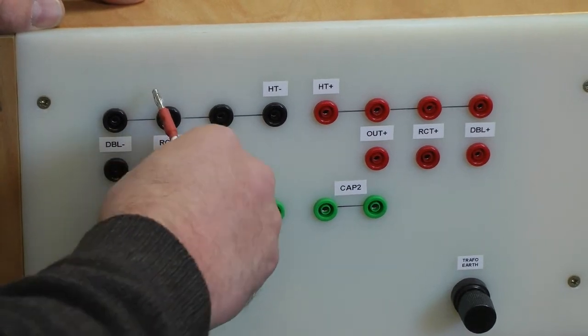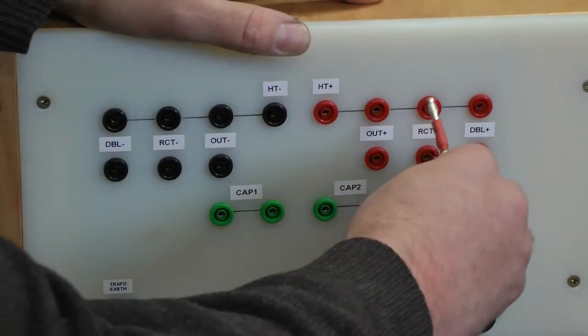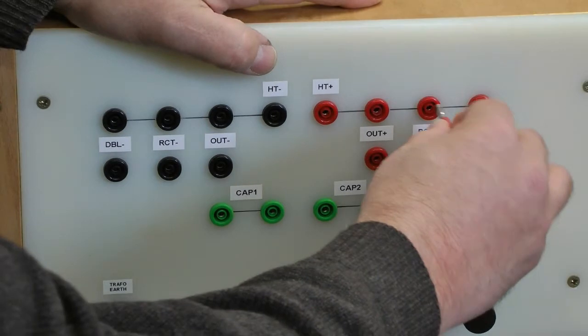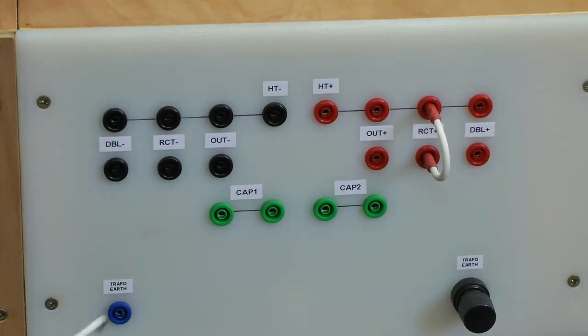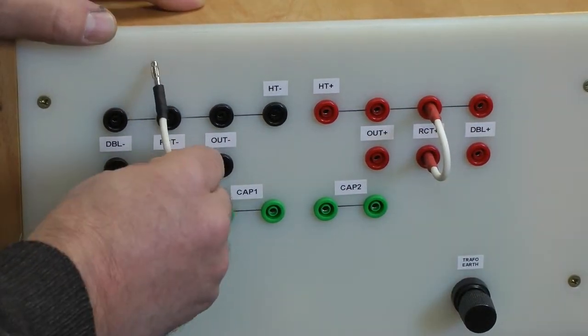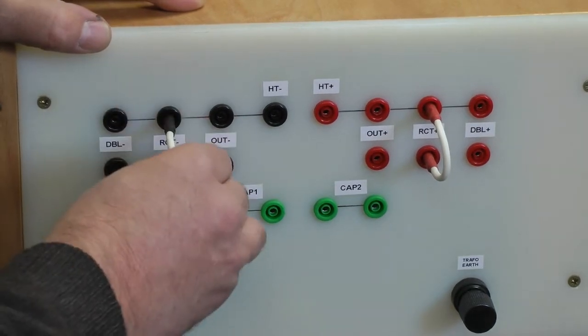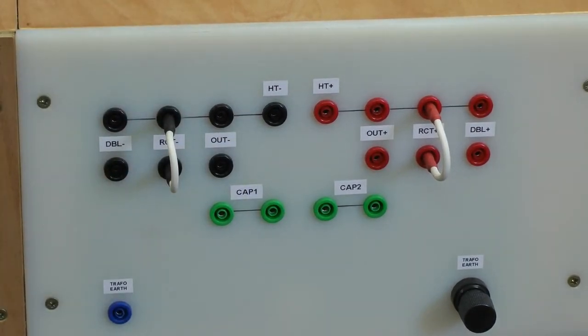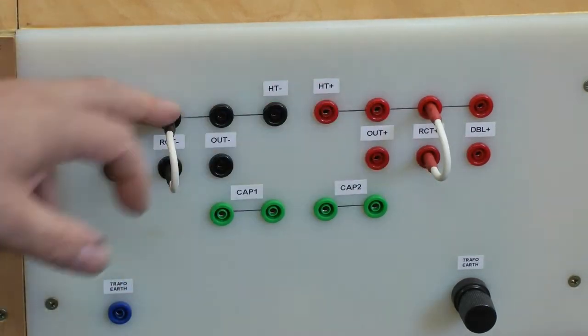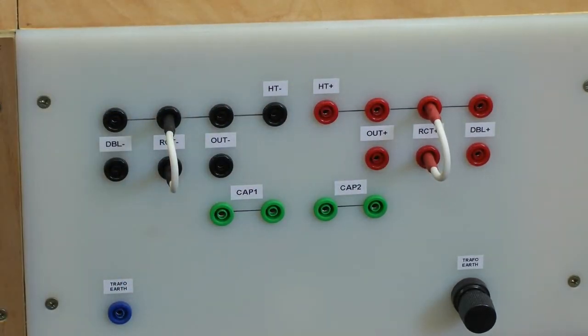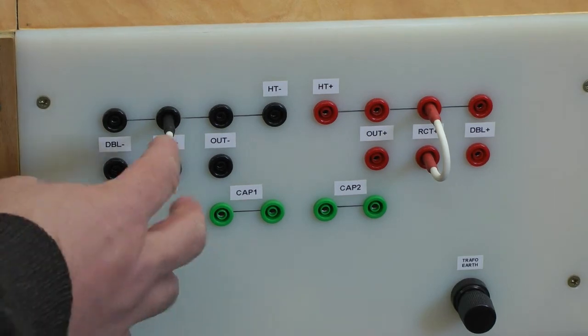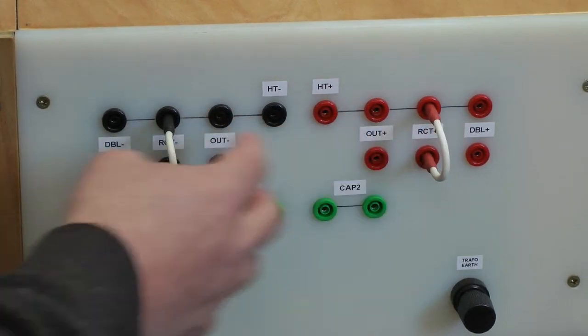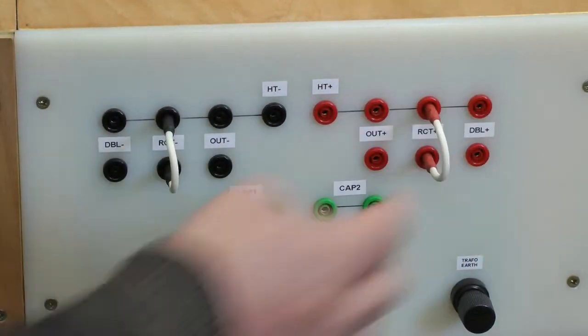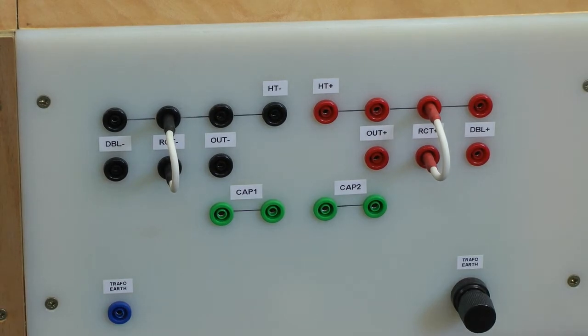So let's get the red one on the red side. So that's the rectifier. So the transformers, if they are internally connected to the high voltage bridge rectifier, then this output now comes to the HT output. If I were to move those there, I can get the raw output. If I move them out to the doubler, then it will be the output of the doubler or level shifter.